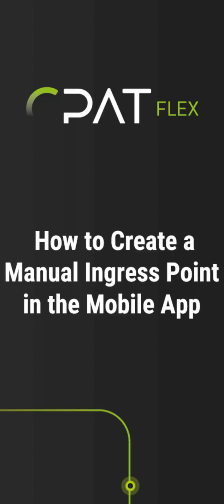This video will show you how to create a manual ingress point with the CPAT mobile app. The reason you would want to do this is that when you use an ITX2 ingress transmitter in manual mode and you're using your phone to monitor the ingress levels, there's no GPS coordinates transmitted with the ITX2. This is unlike when the ITX2 is installed in your truck and it receives GPS coordinates from the ARD4. So therefore any ingress points will be geolocated and plotted on the map.